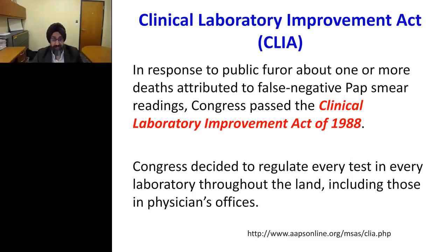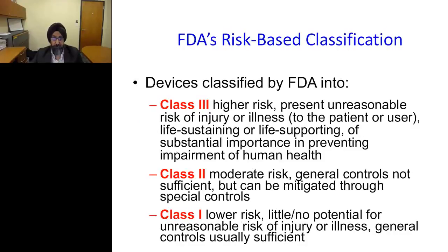The Clinical Lab Improvement Act was passed by Congress in 1988. The purpose was for Congress to regulate every test in every lab throughout the country, including physician's offices. FDA was also given responsibility to monitor the risk associated with various lab tests and the devices used to perform testing. FDA has classified these devices into three categories. Class III devices present unreasonable risk of injury, illness, or can be life-threatening. Class II devices have a moderate risk where general controls are not sufficient but can be mitigated through special controls. Class I devices, which have lower risk, can be waived by the FDA.